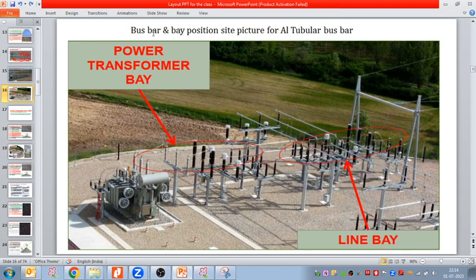Sir, if we choose the aluminum conductor busbar, in that case we'll have to design it for short circuit forces, and sag tension calculations are also to be done. To avoid that, we can opt for tubular busbar.